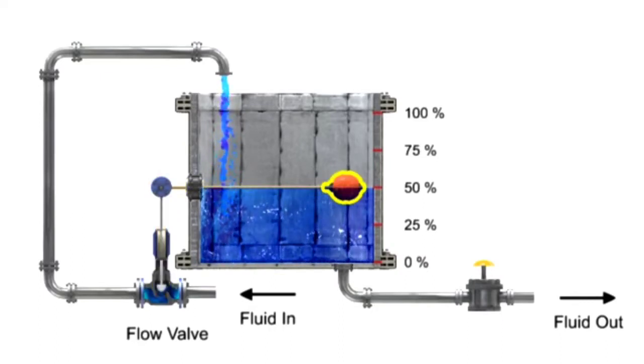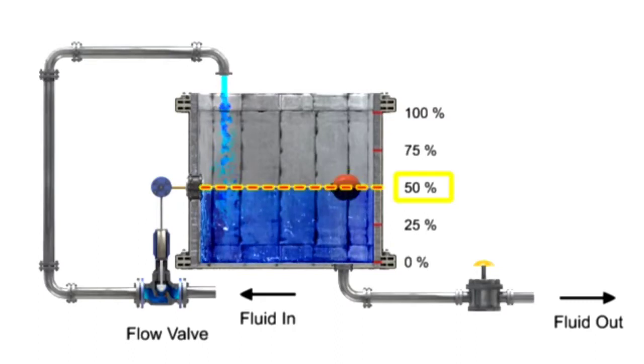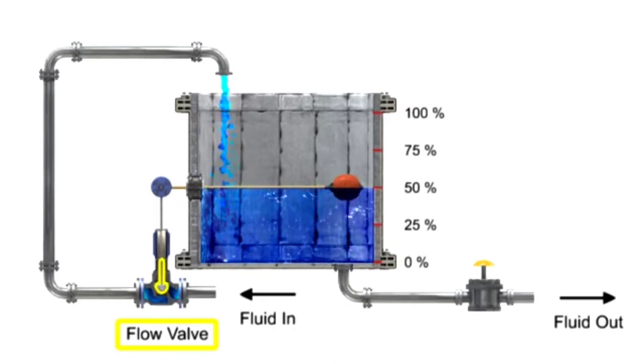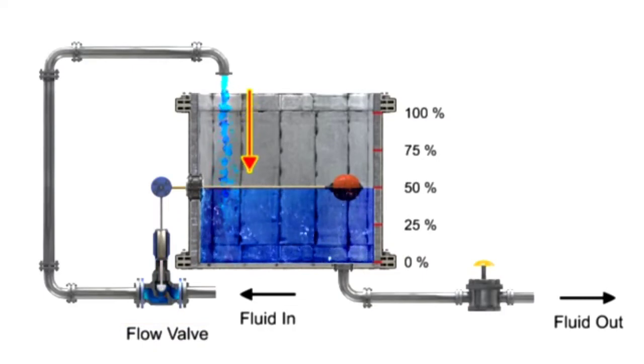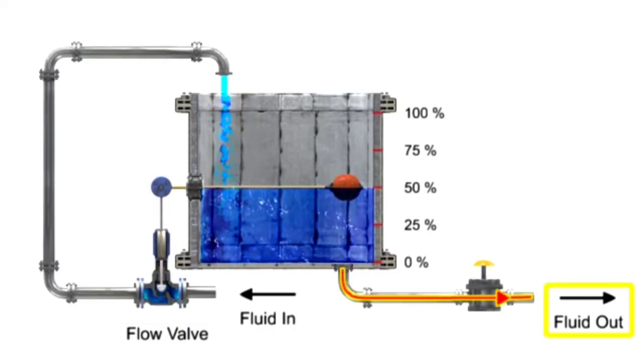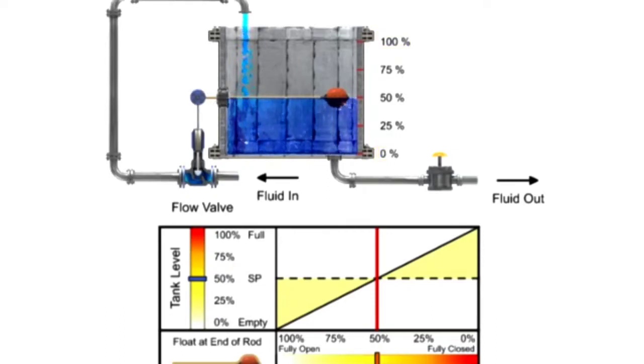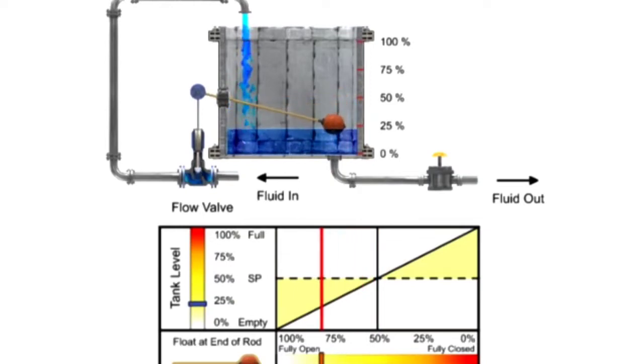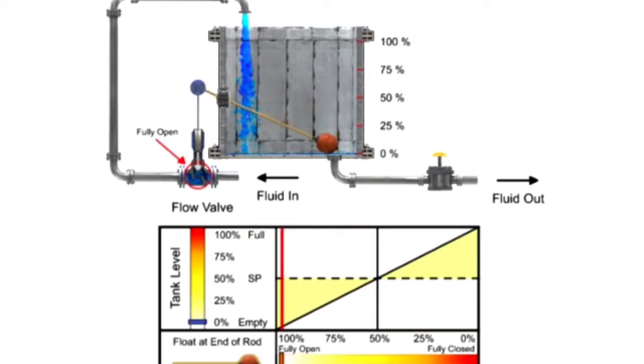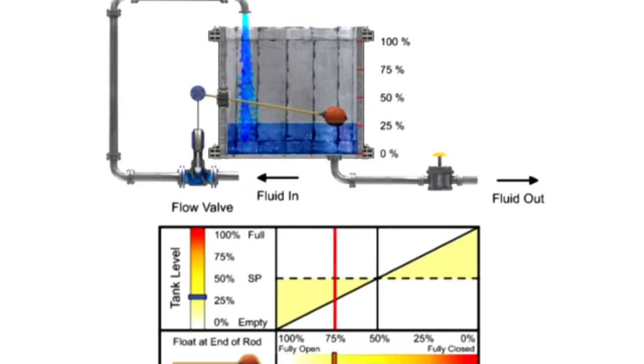The float mechanism is designed so that when the tank level is half-full, the flow valve is open to the position that causes the amount of fluid entering the tank to be equal to the amount leaving the tank. The float on the end of the rod is positioned to meet the minimum and maximum flow capability of the valve. The valve is actuated by the float to a fully open position when the tank level is low, and fully closed when the tank level is full.